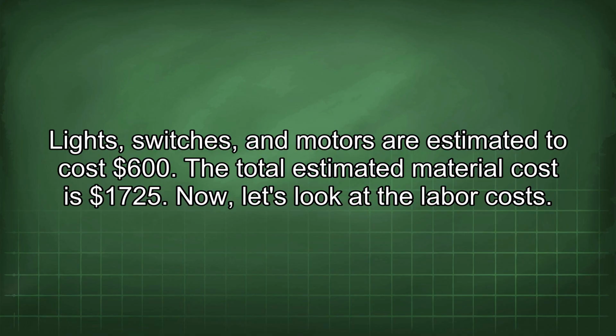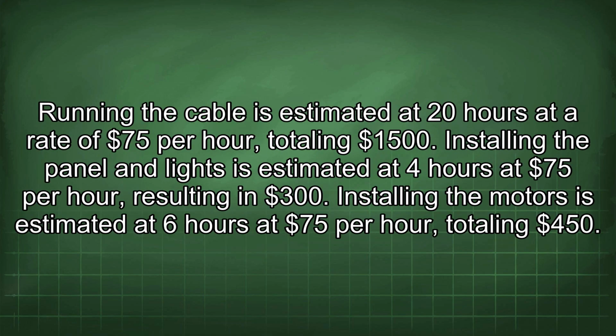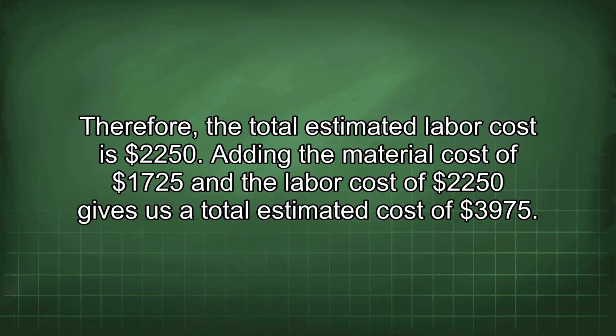Now let's look at the labor costs. Running the cable is estimated at 20 hours at a rate of $75 per hour, totaling $1,500. Installing the panel and lights is estimated at 4 hours at $75 per hour, resulting in $300. Installing the motors is estimated at 6 hours at $75 per hour, totaling $450. Therefore, the total estimated labor cost is $2,250.